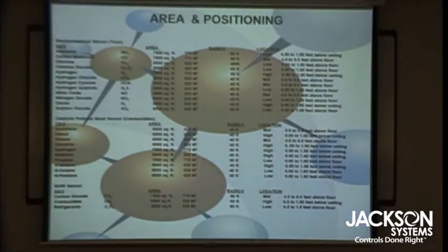This is just when you're looking at placing sensors, what's important is, okay, 2 questions you should ask, 2 or 3. What gas do you want, which they normally tell you. But there's 2 considerations. Your radius of coverage, how much will a sensor cover, and where should I place the sensor? So if it's heavier gases, you normally place it close to the floor, about 12 inches off the floor. And of course, light gases like ammonia and natural gas, you want to place close to the ceiling. So this is just basically a chart that gives you a general overview.